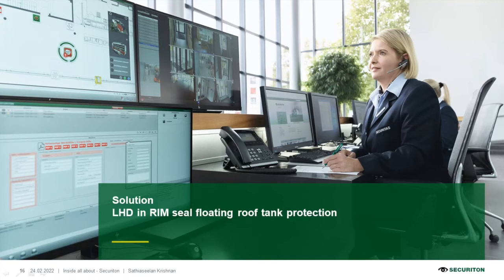We work with LAN and it goes to 100 meters, but in terms of distance, we can use the right proper fiber converters to convert to the distance required on the site, and you can have floating roof tanks far away with our LHDs connected at the control station somewhere else.